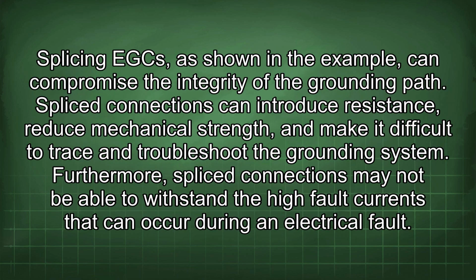Splicing EGC, as shown in the example, can compromise the integrity of the grounding path. Splice connections can introduce resistance, reduce mechanical strength, and make it difficult to trace and troubleshoot the grounding system. Furthermore, splice connections may not be able to withstand the high fault currents that can occur during an electrical fault.